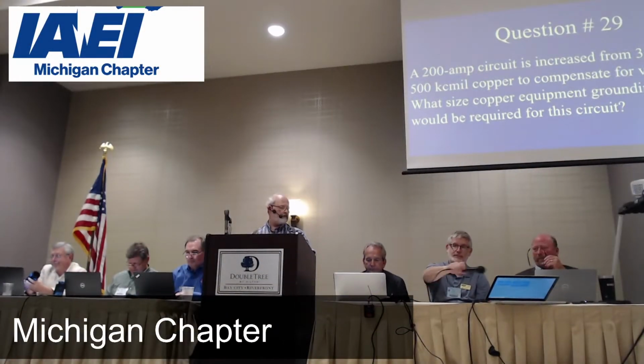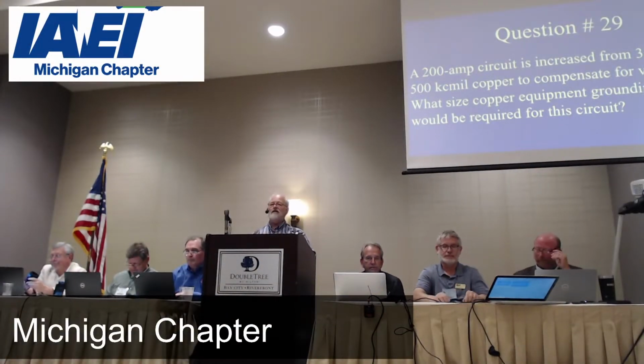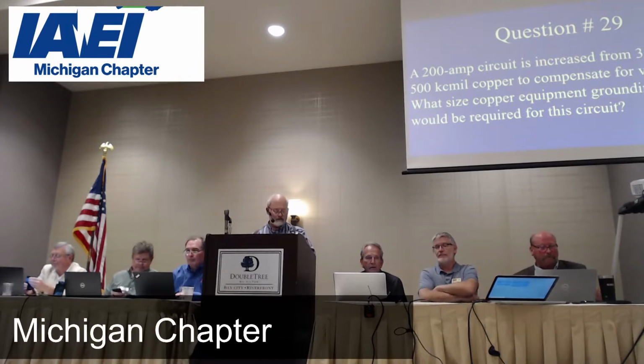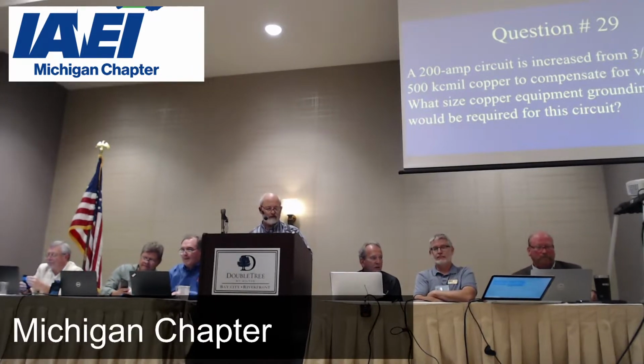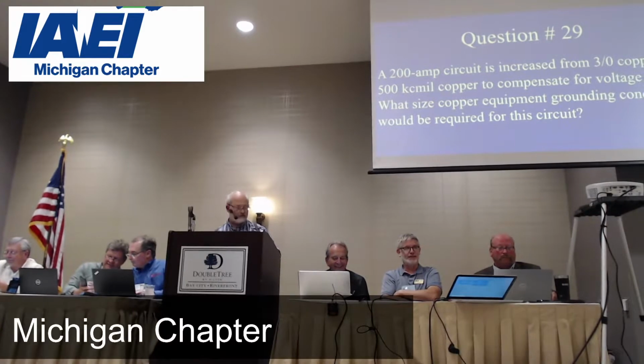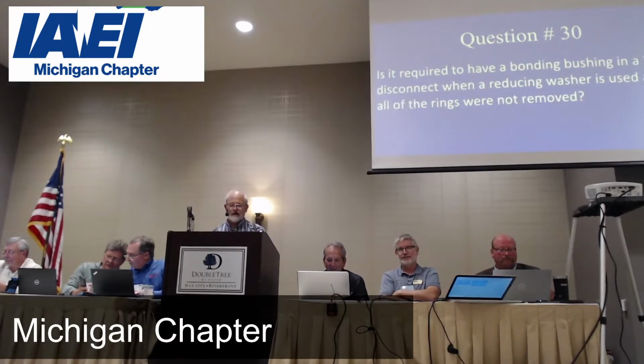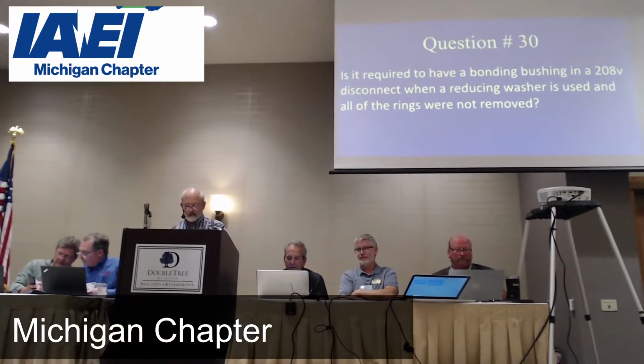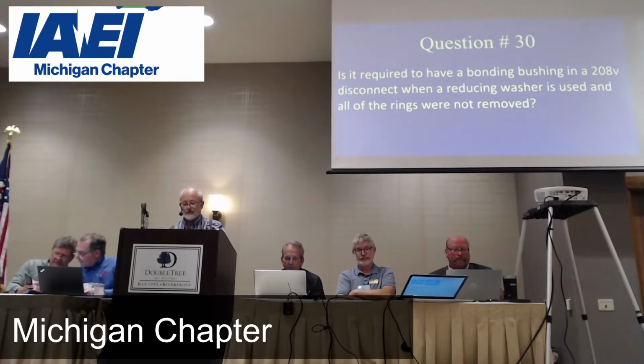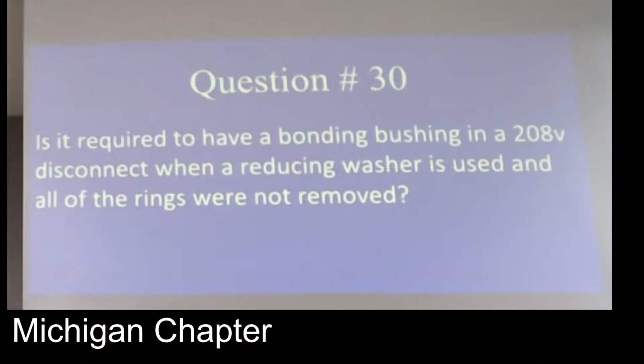Okay. Questions? Comments? Okay. Scott, is it required to have a bonding bushing on a 208 volt disconnect when the reducing washer is used and all of the rings are not removed? Yep, so I'll turn the mic on first.